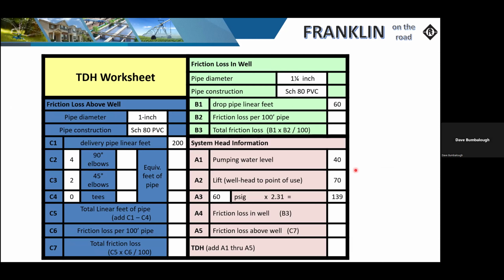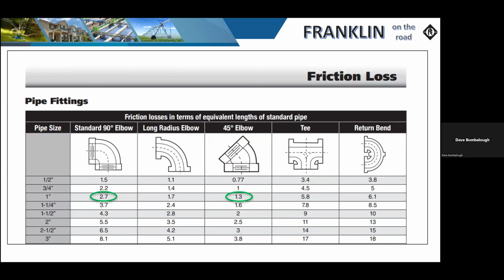And then our operating conditions, the system head information. We have the pumping water level set at 40. We've got an elevation change of 70 feet. And then we've got to satisfy our 40/60 switch. So we're taking the bigger number times that 2.31, which is equivalent to 139 feet of head. So as we add those up, we go back and grab those numbers that are equivalent to the 90.